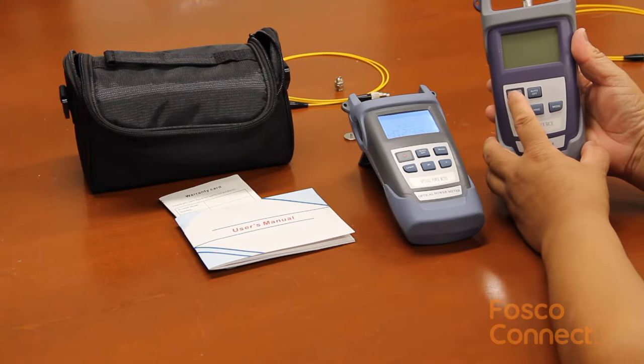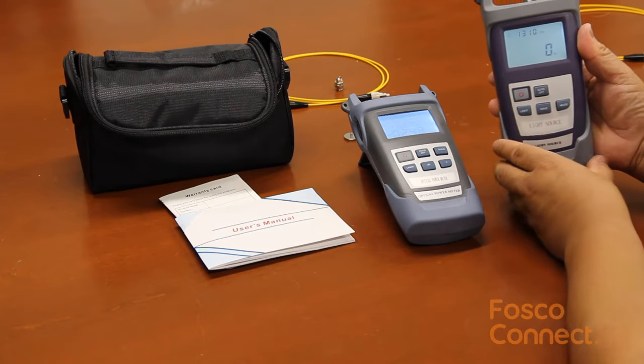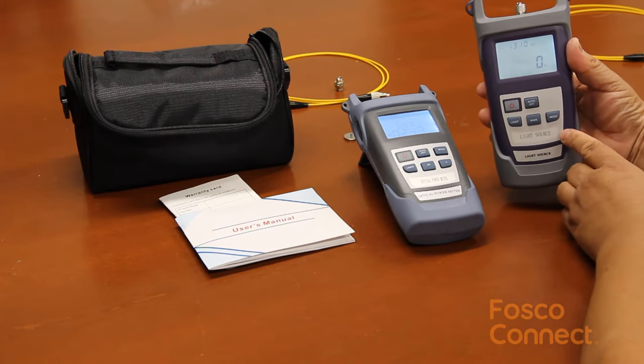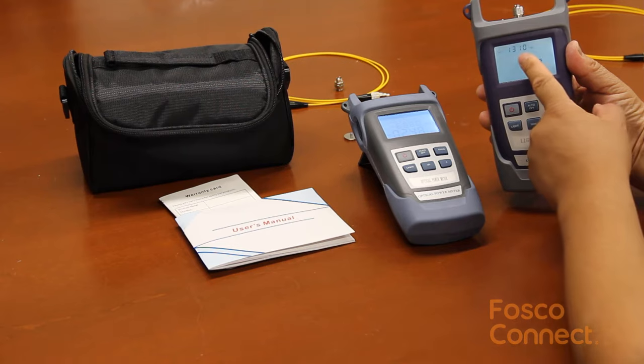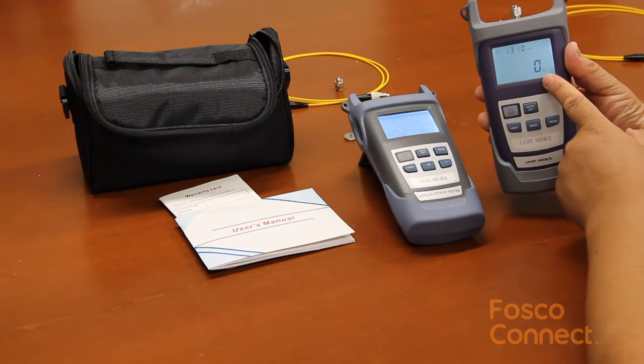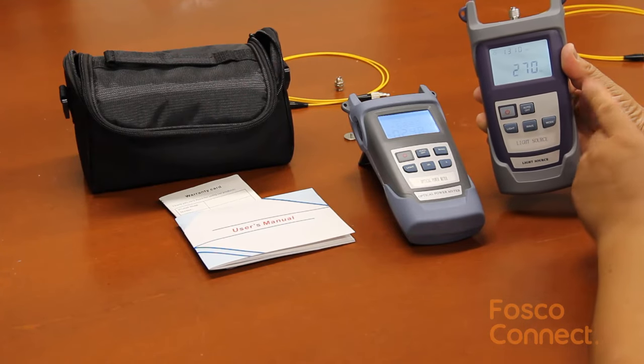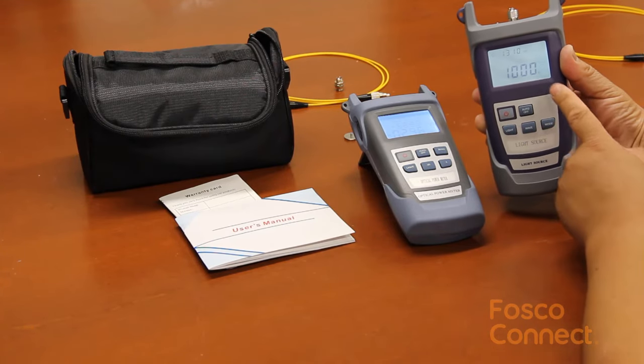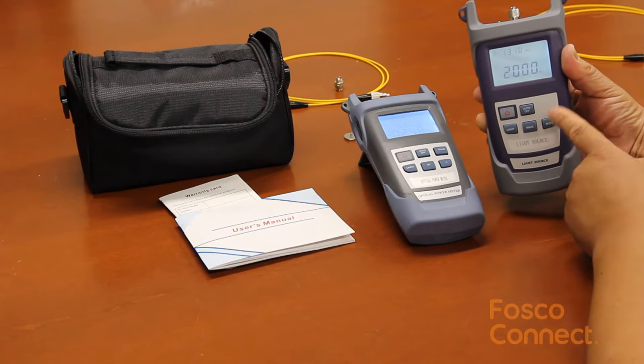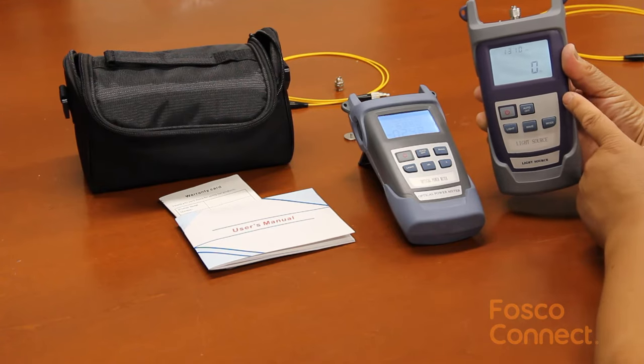Here is a handheld single mode laser light source. Let's turn it on. Now it is emitting light at 1310 nanometer single mode at steady continuous mode. We can switch it to 270 hertz pulse mode, 1000 hertz pulse mode, 2000 hertz pulse mode, and we are switching it back to zero hertz steady continuous mode.